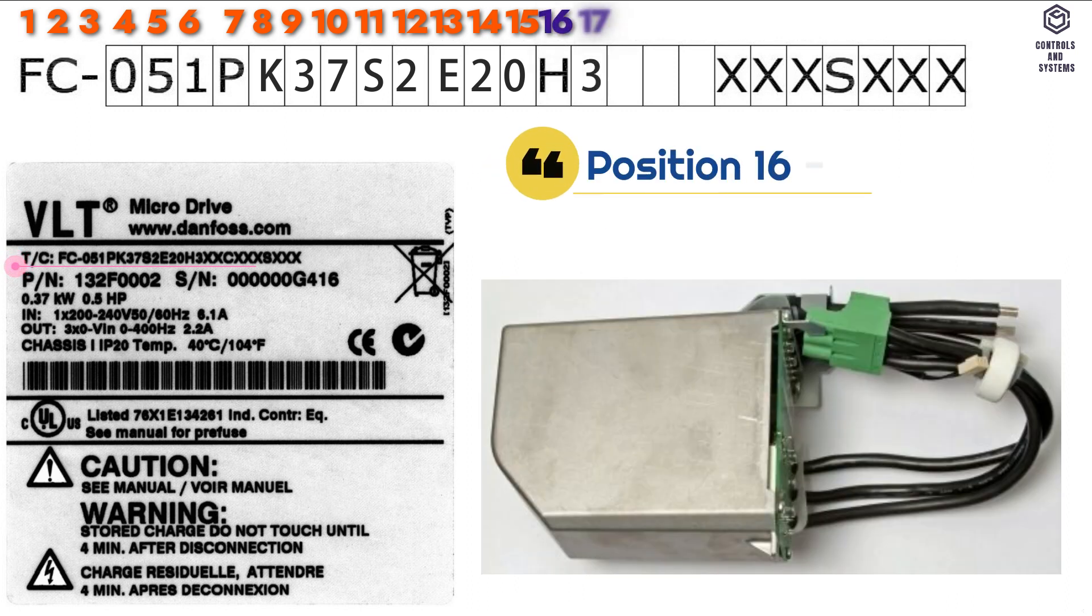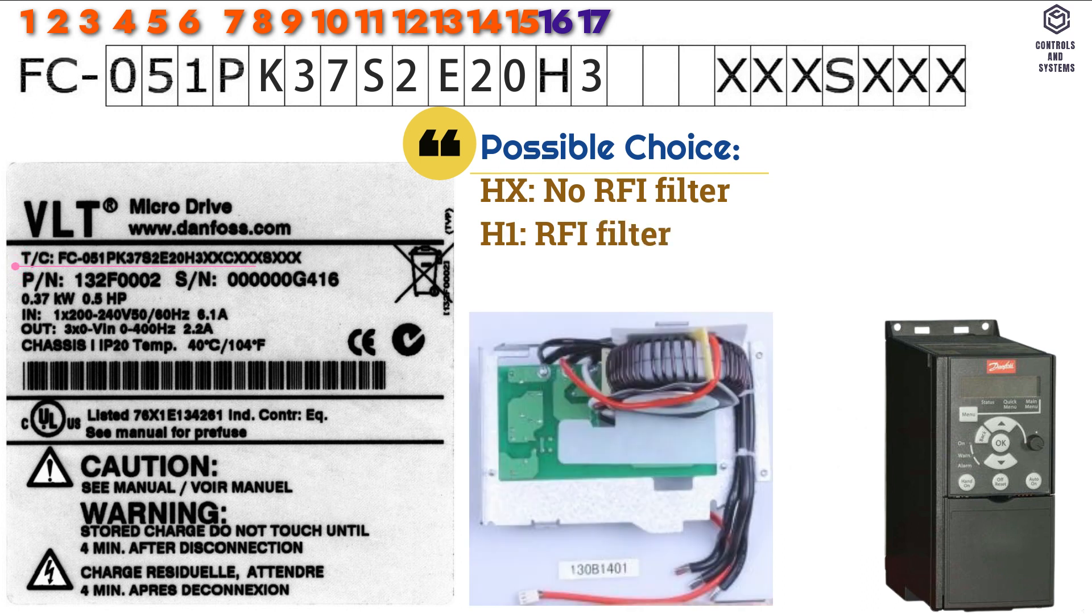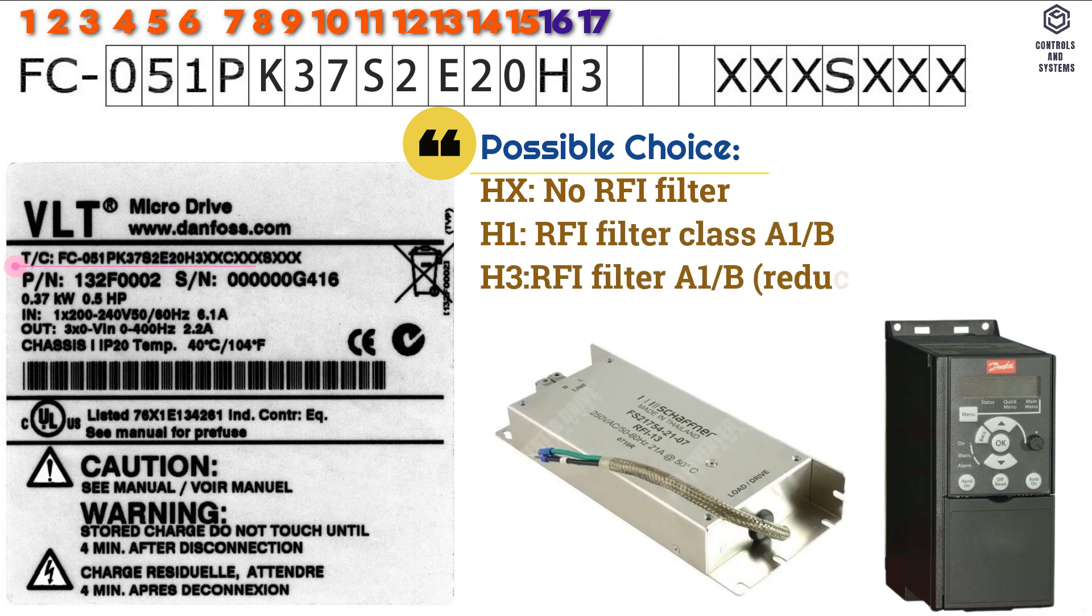Position 16 to 17 is RFI filter, possible choice is HX that means no RFI filter, H1 that means RFI filter class A1 slash B, H3 that means RFI filter A1 slash B reduced cable length.